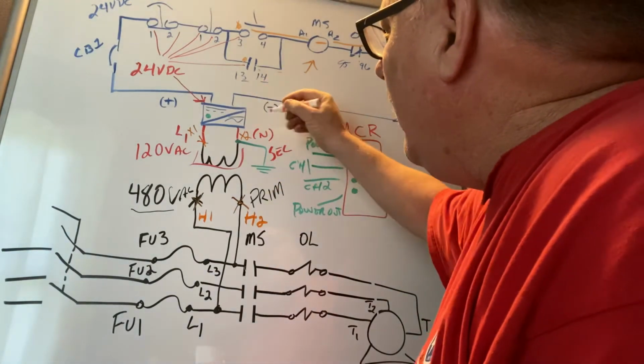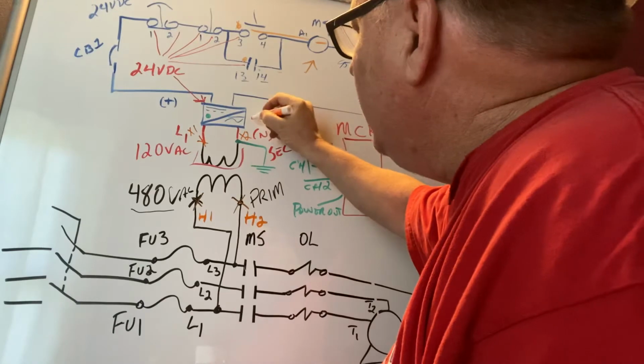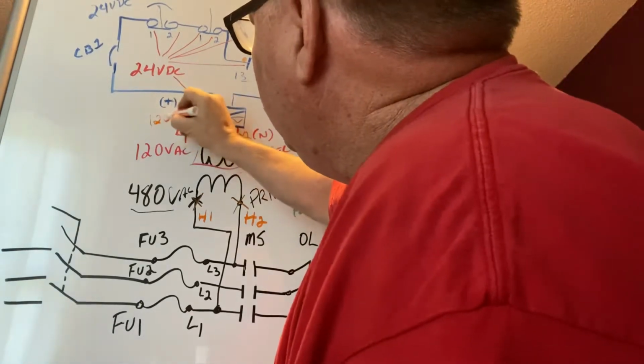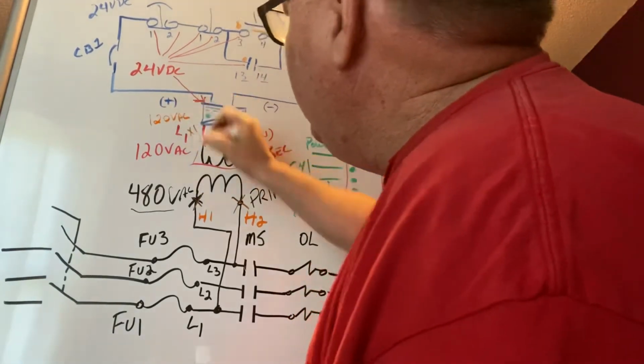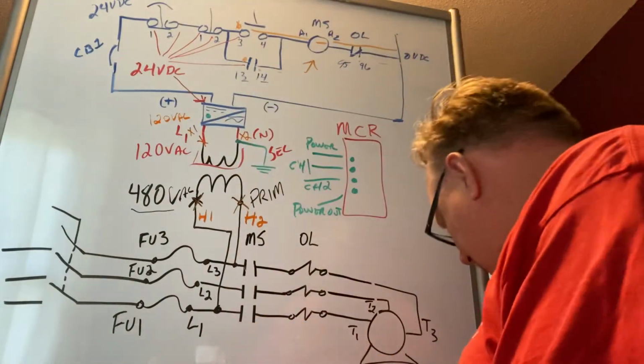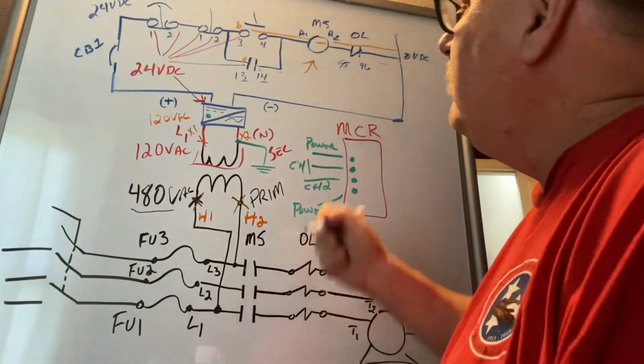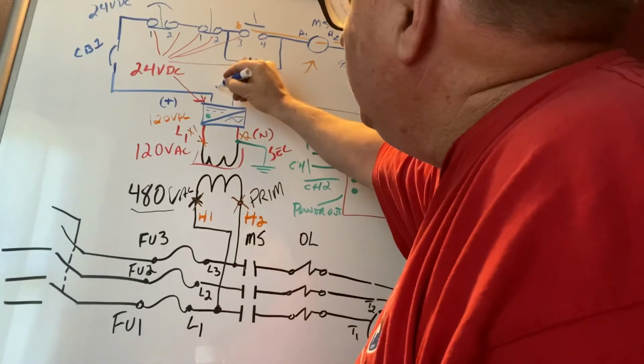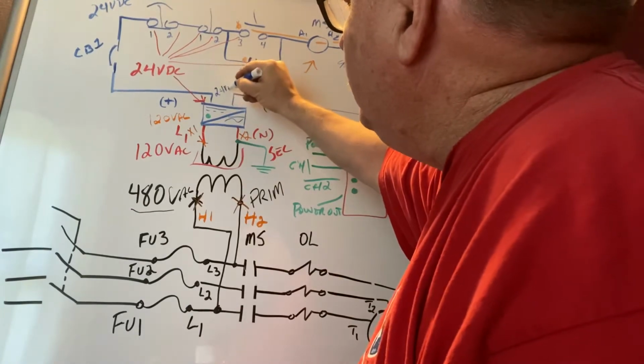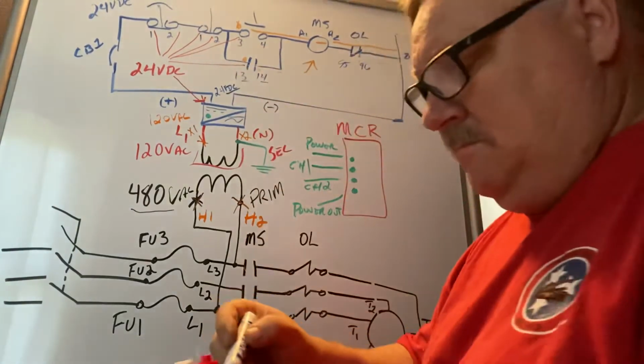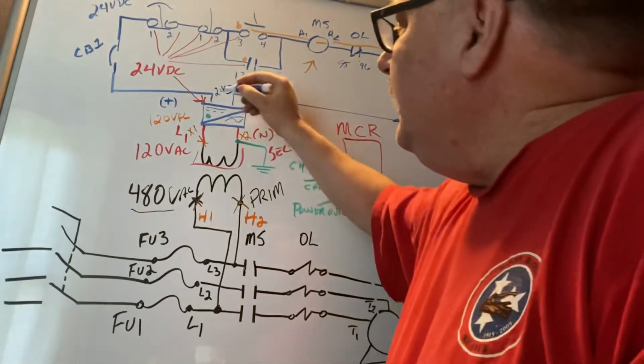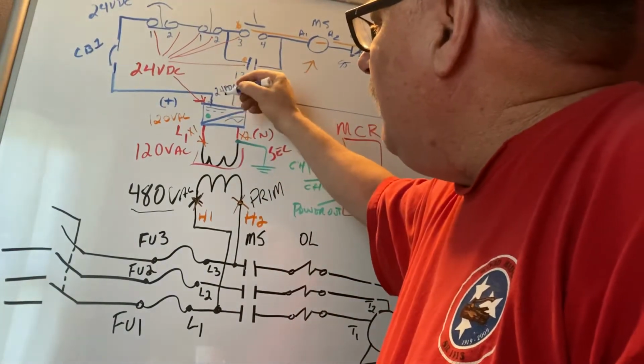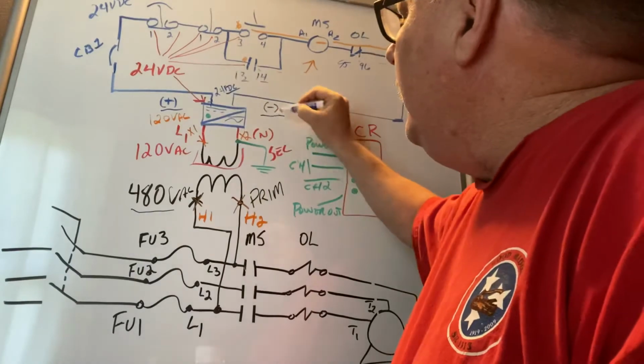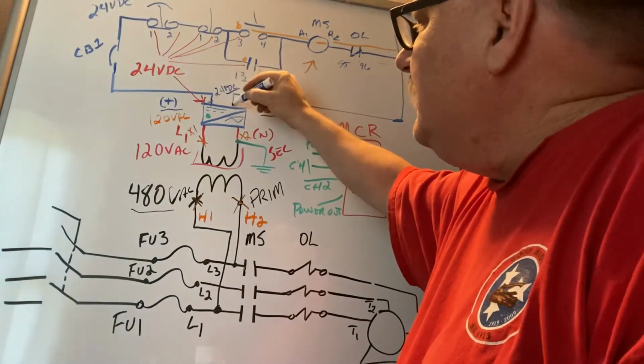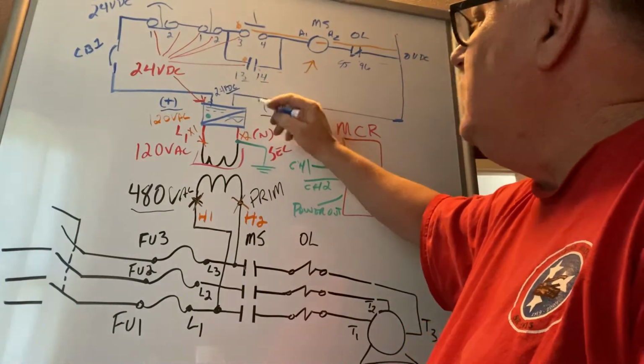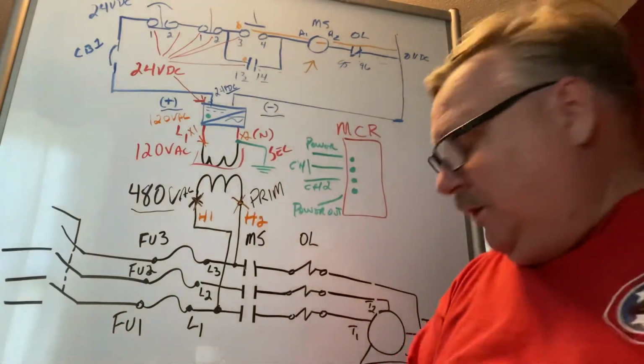On your power supply, on your input side, you'll see that 120 volts AC, okay? And on your output side, you'll see 24 volts DC, okay? And that should be at each one of your terminals. You're going to have a positive side, which I've got here, and a negative side. So if you go positive and negative, you should see 24 volts.